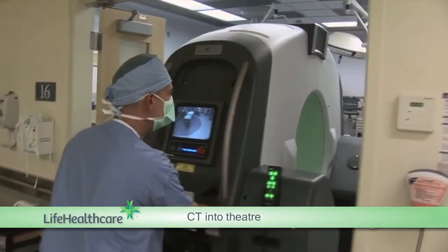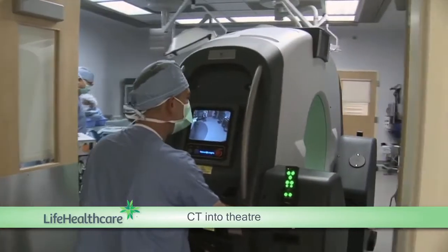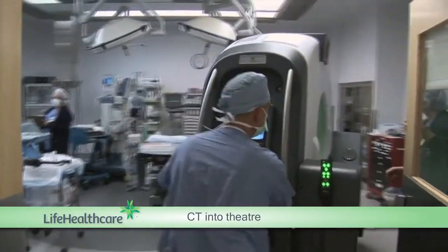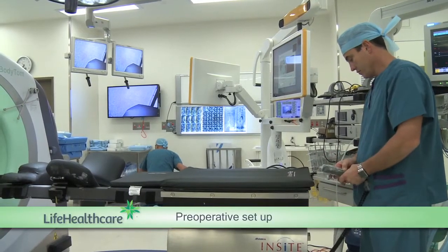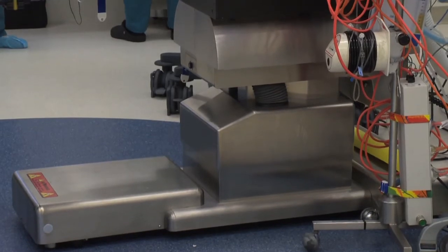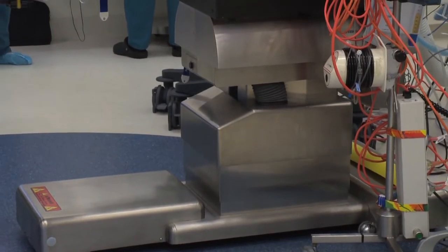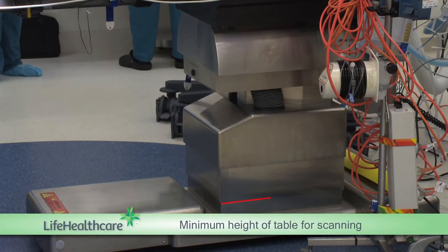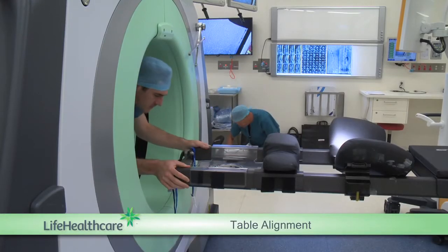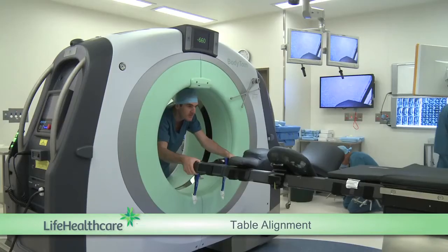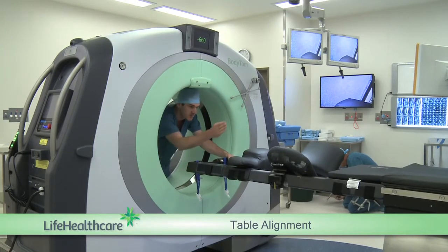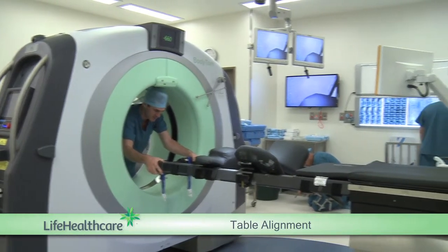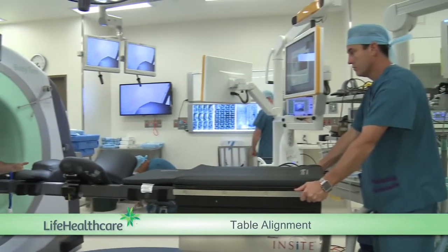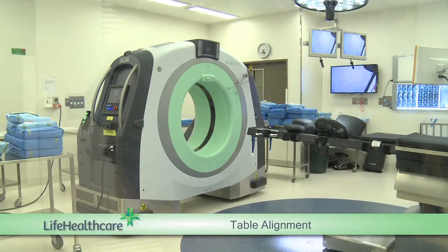In this case, prior to the surgical list, the BodyTom is driven into the theatre and positioned where the scan will be initiated. The table is raised to the minimum height required to clear the gantry, as shown by the line highlighted here. The radiographer or theatre staff will align the table at this time, and once the proper alignment is achieved, the table's floor lock is enabled. The system components are now optimally positioned to allow smooth workflow once the operation has commenced.